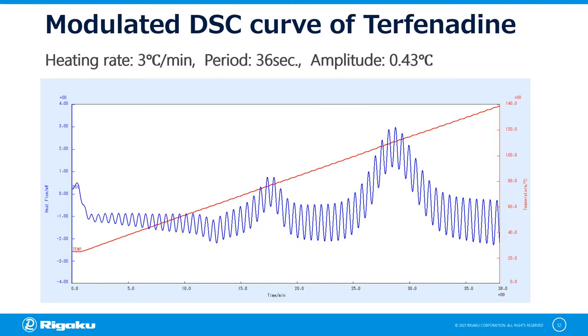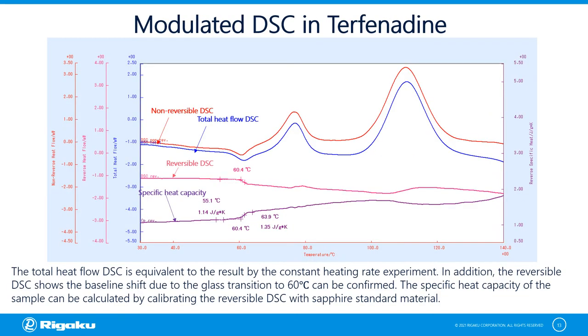This is the measurement result of Terfenadine with dynamic DSC. This was measured with a heating rate of 3°C per minute, a period of 36 seconds, and an amplitude of 0.43°C. Data analysis is performed to separate the reversible component, which is the specific heat capacity component, and the non-reversible component. The result of modulated DSC in Terfenadine is shown here, where the reversible heat flow is extracted from the DSC result and separated from the non-reversing heat flow.